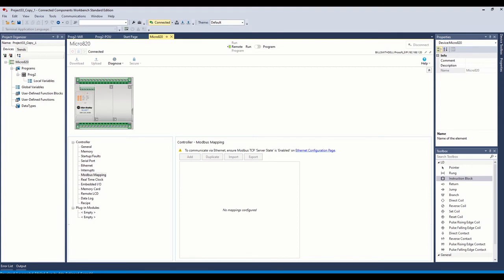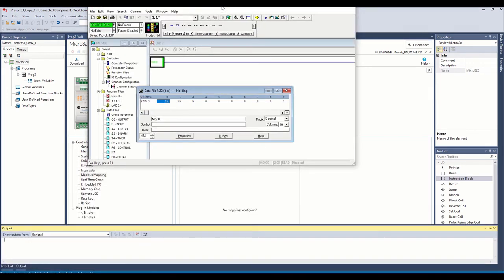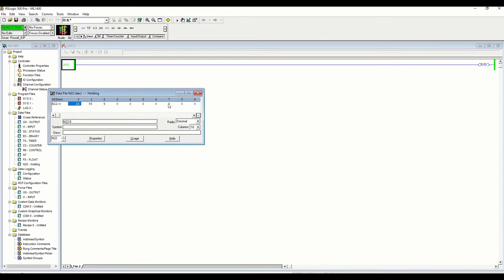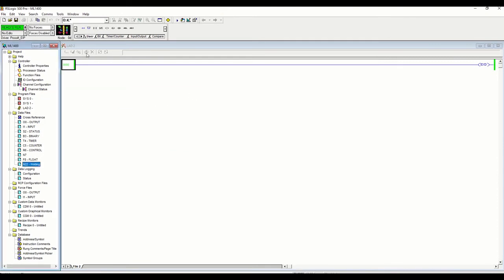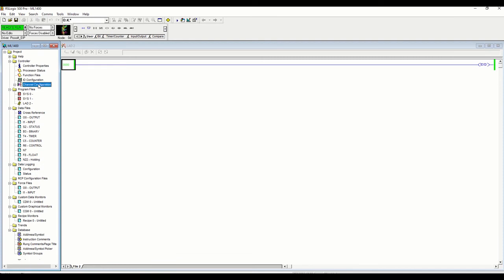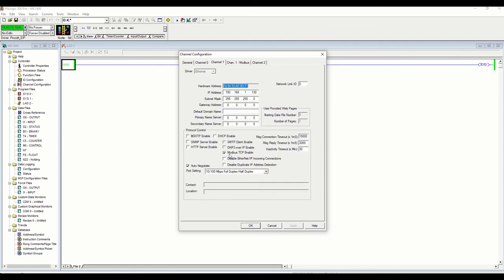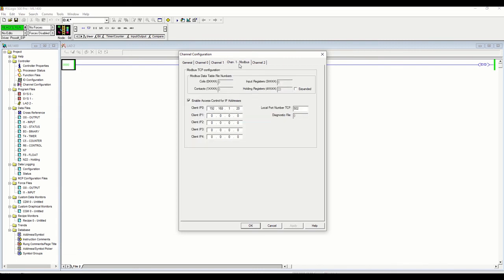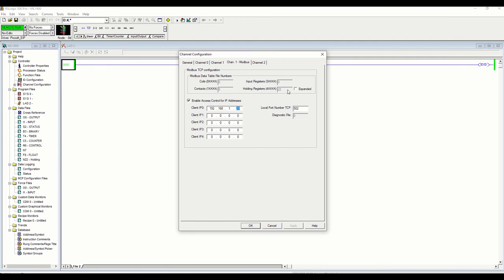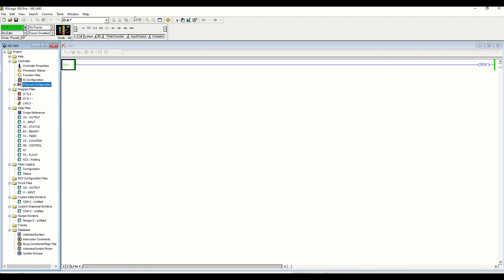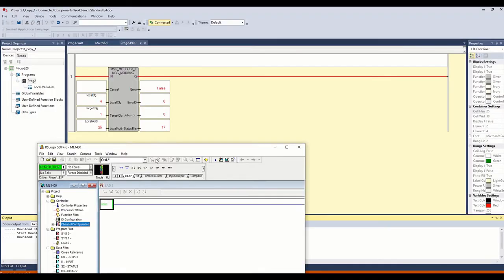And while that's doing that, I wanted to show you on the other end, this is the MicroLogix 1400 program that I have running on the same little network. If you come under channel configuration, and then channel one Modbus or under channel one, first of all, I have the Modbus TCP enable checked. And that gives me access to this channel one Modbus and I'm allowing access to our Micro 820. And I'm also mapping our integers N22 to our holding registers. So N22 zero is 40001. So that's how easy it is to make a MicroLogix a Modbus slave. So that just so you know, that's what we're doing and that's where our data is going to be coming from.